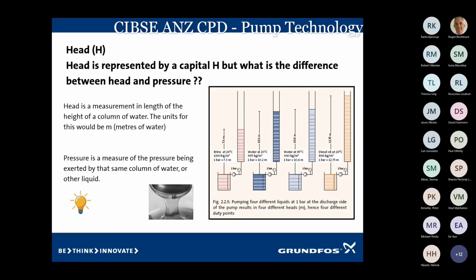If somebody calls you up and says, look, my pump keeps overloading, it might be a vineyard, for example, and the pump's running out towards the right-hand end of the curve, what's happened is that the product's so much denser, you've just taken up all the extra motor power, and it can't do it, it'll overload.